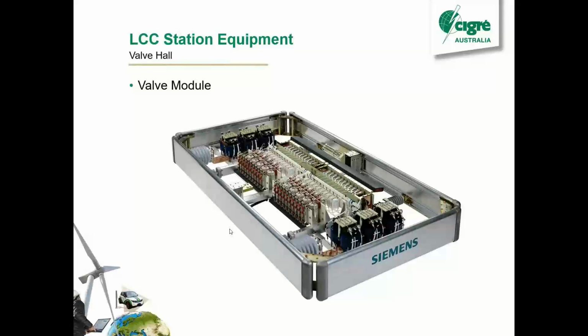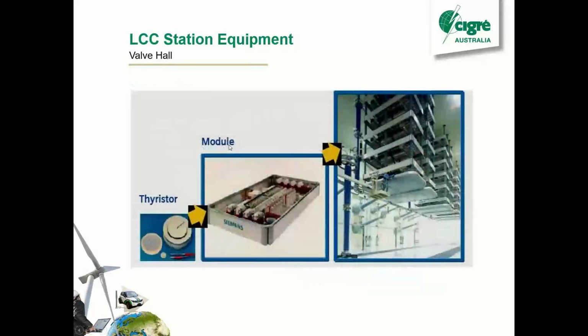So this is a valve module that you'd find in a valve hall. I said each one of those thyristors we were looking at on that 6-pulse bridge is actually made up of lots of thyristors in series. So you can see the thyristors stacked up here. We've also got some snubbers. Each thyristor will have a snubber, an RC circuit, to help with the switching and sharing the voltages. And then we've got these reactors at each end as well, to help with smoothing out the current during the switching. So the way you build it, you start with a thyristor, you add it into a module, and then you stack up your modules to get what you need.